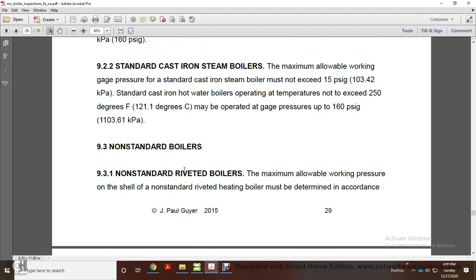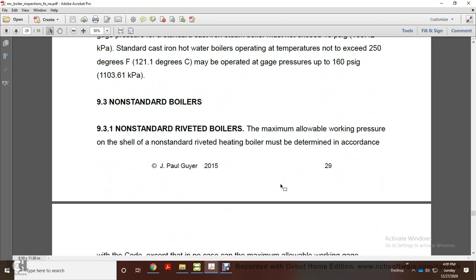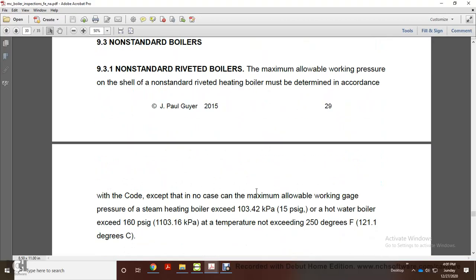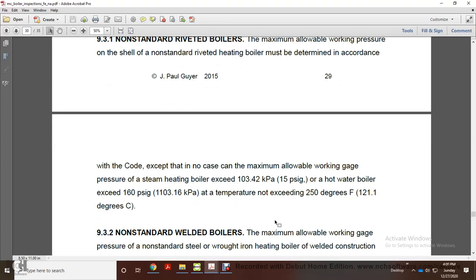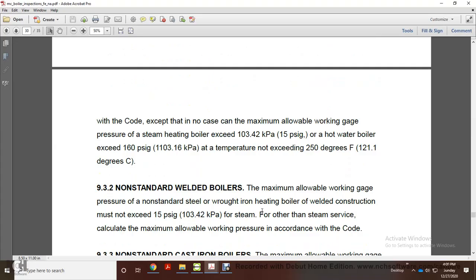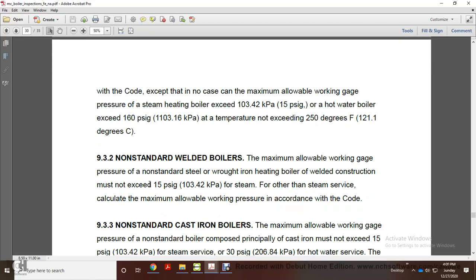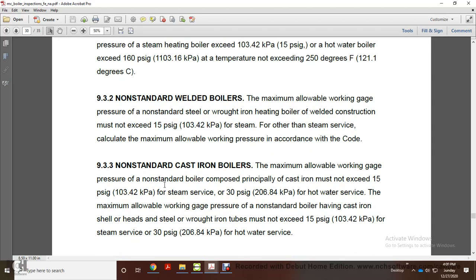9.3 Non-standard boilers. Non-standard riveted boilers: the maximum working pressure on shells must be determined in accordance with the code, except that in no case shall the maximum allowable working gauge pressure exceed 103.42 kilopascals for a steam heating boiler, or 160 psi gauge for a hot water boiler at a temperature not exceeding 250 degrees. 9.3.2 Non-standard welded boilers. The maximum allowable working gauge pressure for non-standard wrought iron heaters of welded construction must not exceed 15 psi gauge for steam. For other than steam service, the maximum allowable working pressure is calculated in accordance with the code.